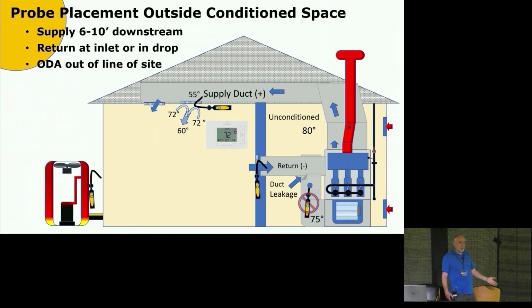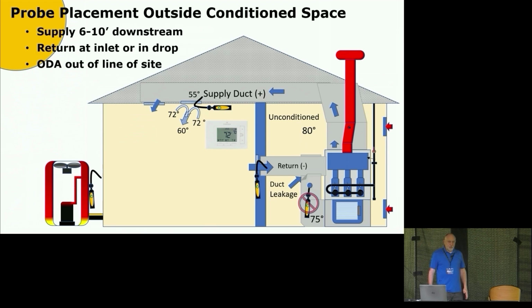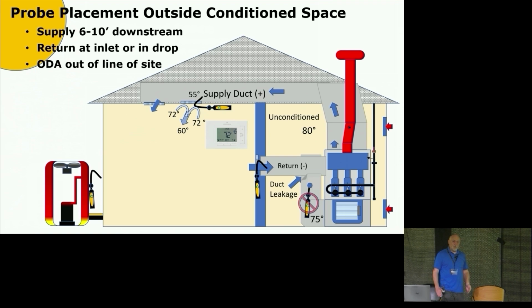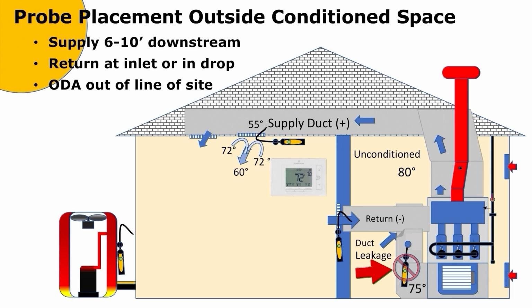right? Now this is what's crazy. There are so many techs out there that will see a poor temperature split. They'll see like a 16 or 12 degree split. What's the first thing they do? Walk in and slow down the fan, right? Oh, temperature split's wrong. Nobody ever set this, the fan speed's too high. They slow down the fan and they just missed the duct leakage issue. Completely missed it. Because they're seeing 75-degree return air coming in there that's hot air leaking in from that unconditioned space, right? So probe placement is absolutely critical on the software to make sure it comes out with the right answers.